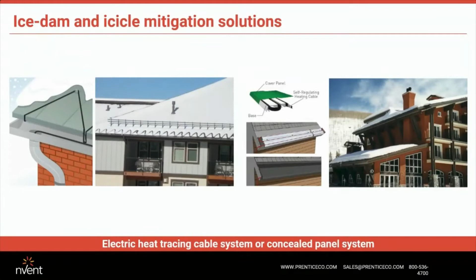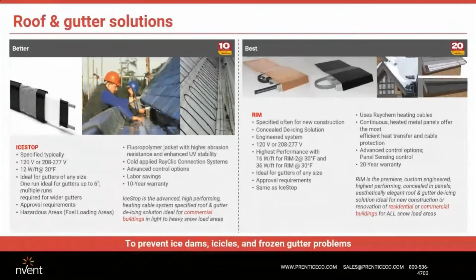One thing to note with nVent Raychem products: we offer the highest output rating as well as the highest extended warranty. With the IceStop heat trace cables, once tested and applied for, we'll give a 10-year extended warranty, validated. But when you put it inside the metal enclosed systems, that's now extended to a 20-year warranty—the best in the industry—because it's protected in the aluminum enclosure, though we still have to validate and ensure testing has been done to be compliant.